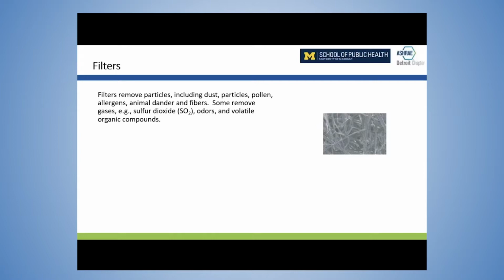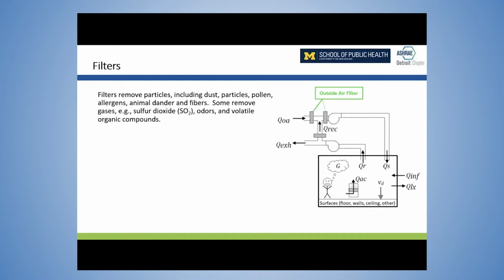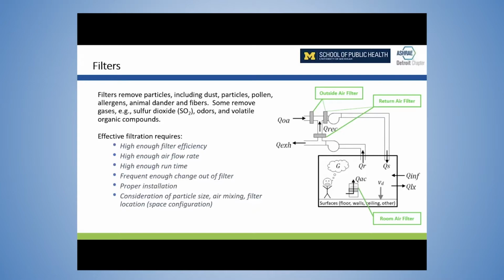My last topic before I turn it over to Sonia is to talk about filters. On the right, we see a typical fibrous filter. These can remove dust, particles, pollen, virus, and so forth. So a mechanical system, as I'm showing here, has opportunities to have filters in several places. You can have outside air filters, treating simply the outside air, or the combination of outside air plus return air. Next slide. We also have a mixing box typically doing recirculation. You can have a filter there. Next slide. And then finally, adding a personal or a portable air cleaner or room air filter can condition the air in that space.